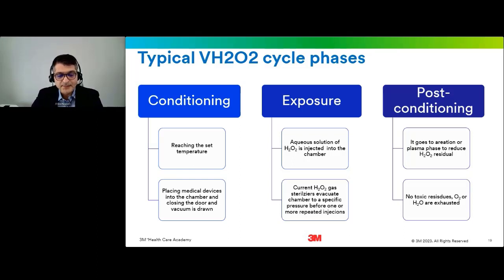The next phase is the post-conditioning phase. In a plasma system, the cycle will go to the plasma phase. If it's not plasma, it will go to the aeration stage. The plasma will change the remaining hydrogen peroxide to water and oxygen molecules. In systems that use hydrogen peroxide plus ozone, in the exposure phase, after each injection of hydrogen peroxide vapor, ozone is also injected.